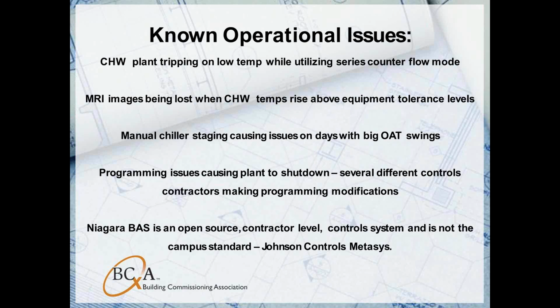So while interviewing the facility staff, we learned about some fairly major operational issues that they were experiencing. We learned that the chilled water plant was frequently tripping out on low temperature alarms. This building in particular utilizes a series counterflow configuration for a few of the chillers in their plant. And so with a low delta T issue in the building as well, they were having a lot of low temperature trips on their chiller plant. Because of this, the MRIs on the third floor of the building were losing images, and when this would happen, they would lose a lot of the big revenue generators in the building. So MRIs and CTs are big revenue generators, and they were losing images. So, you know, unhappy tenant when that happens.